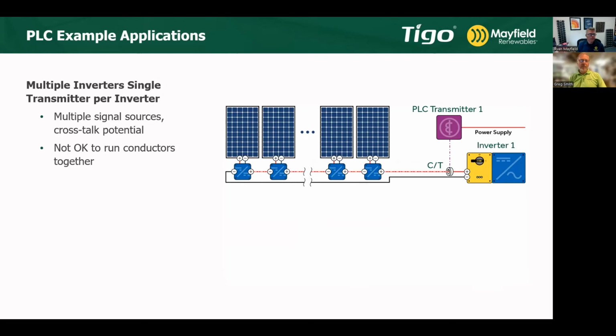Okay, let's get a bit more complex. If you have multiple inverters, which is common in larger commercial systems, I had to get clarification from you, Greg: when you have multiple inverters, each inverter needs its own transmitter. Correct. You cannot share a transmitter with multiple CTs across multiple inverters. So when we have multiple inverters, we will have to have multiple transmitters.